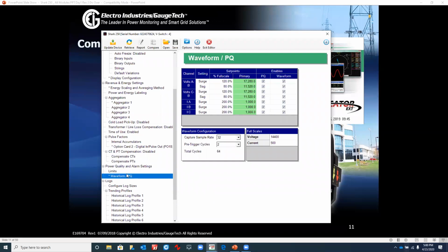Your waveform, which is another thing in this meter, provides waveform capture, which gives you the ability to capture up to 512 samples on this meter. And that affects your trigger size. With 512 samples, you have 2 triggers, pre and post trigger. This gives you the ability to control what you are trying to capture by setting the sample rate. So this is pretty nice. There are waveforms that are generated as a result of setting these parameters.